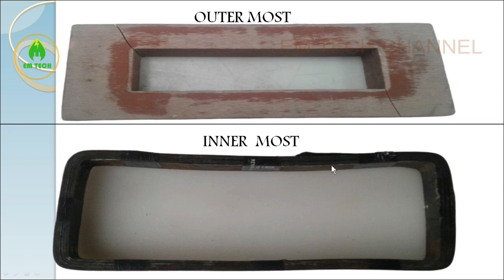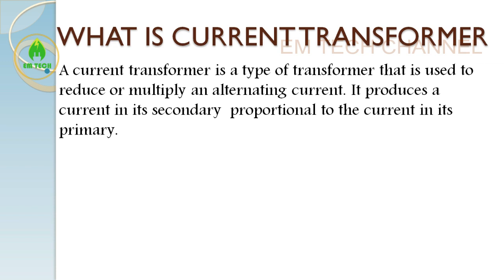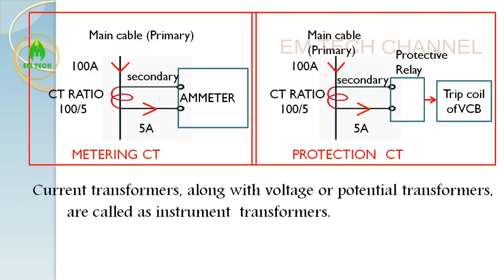Before that, let us discuss what a current transformer is and what the types are. A current transformer is a type of transformer used to reduce or multiply an alternating current. It produces a current in its secondary proportional to the current in its primary. It is used to step down the current flowing in the primary to the secondary for the purpose of metering and protection. For example, if a CT has a ratio of 100/5, and 100 amps is flowing in the primary, the secondary will produce 5 amps.